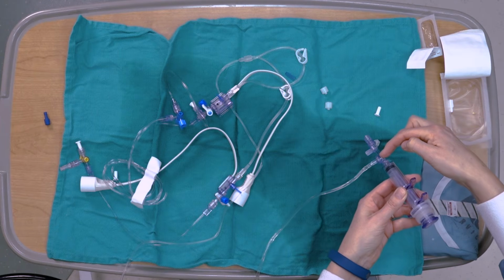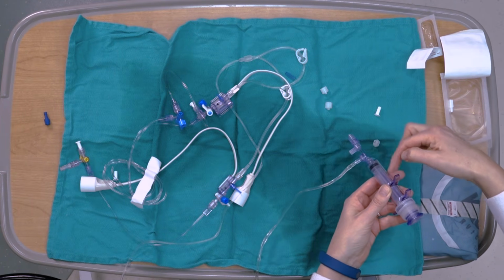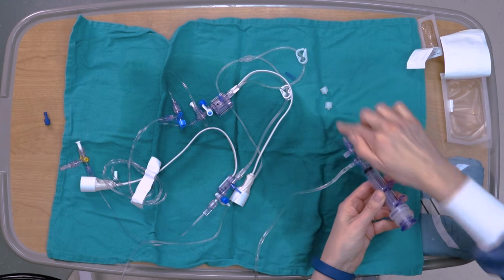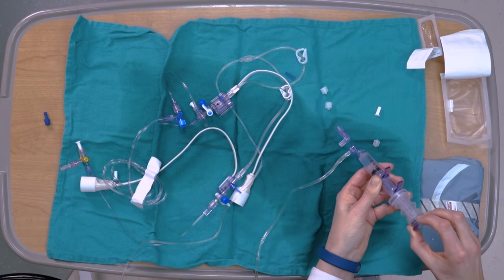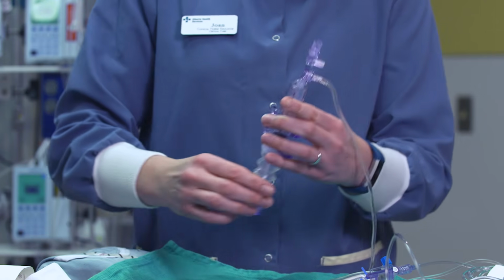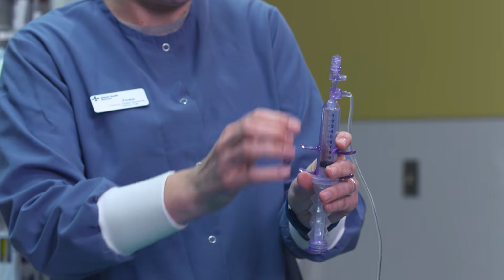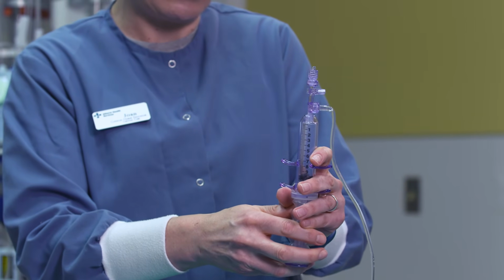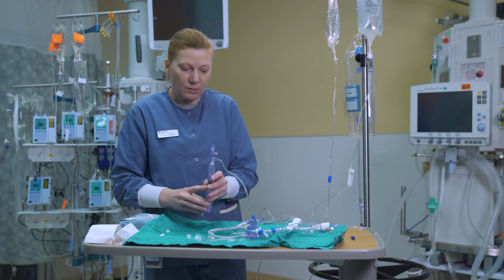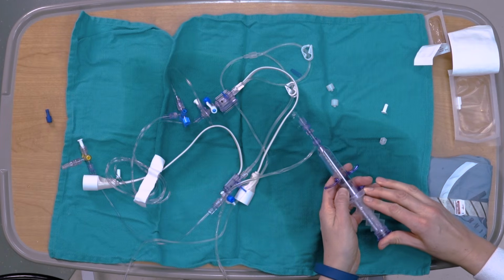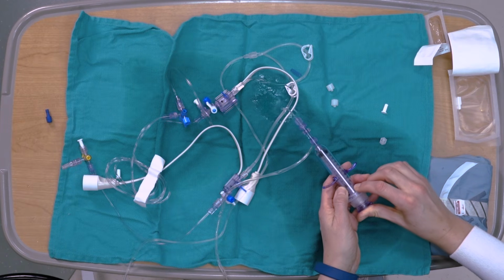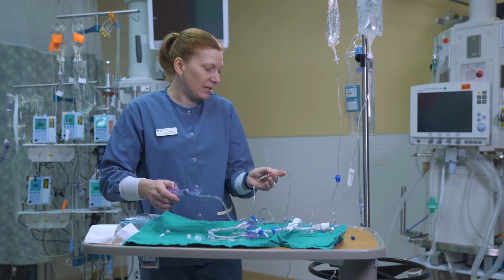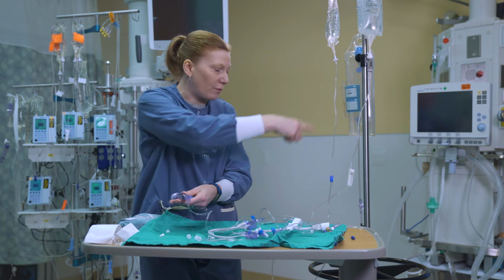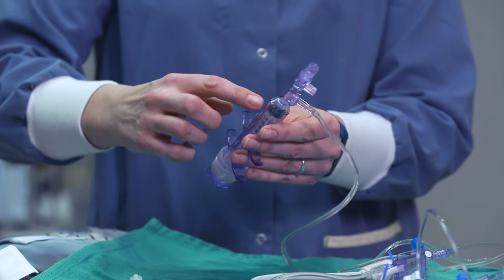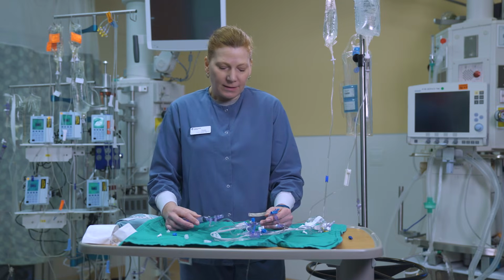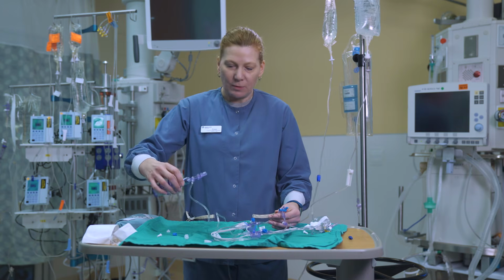So this piece here is actually a one-way valve. So that's going to prevent the fluid, when I push through, from going up. Instead, it's going to come out. So first, we're just going to pull that up. So we're getting some fluid into that syringe. And just like with any other syringe, you're going to make sure your air bubbles are out, so that you're pushing that air out first. Okay, looks good. And I'm just going to get rid of all that fluid right now. And normally it could potentially take a couple times for you to fill the syringe and push out before the fluid has come all the way down. But just make sure at the end of it that you've got that fluid all out of there. Okay, so now that we've flushed the tubing with the cardiac output, we're going to attach it now.